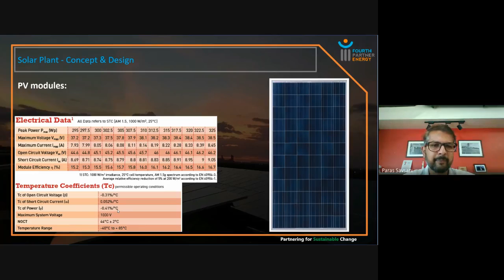So I have specified the string, and the input power is defined based on the number of strings you are connecting. One string is the number of modules connected in series, and the number of strings you are connecting with the inverter gives your total input current. So total input current is your parallel connection. One string has 7 ampere, another string has 7 ampere. So the total ampere can reach, let's say this inverter can be utilized up to 60 or 70 ampere. So you can connect 6 strings together, and that specification is already defined in the data sheet.